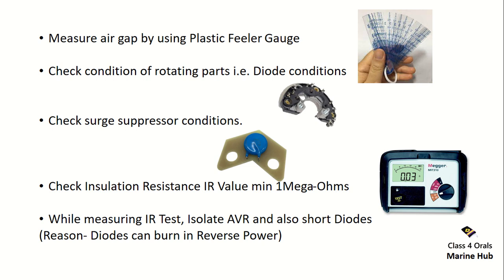Measure the air gap using a plastic feeler gauge — you can see the plastic feeler gauge on the right. Measuring the air gap is a very important question asked in MMD orals. I have made another video on the generator air gap explaining what happens if the gap is less or more, how to measure it, and why we use a plastic rather than a metallic feeler gauge. The link is in the description.